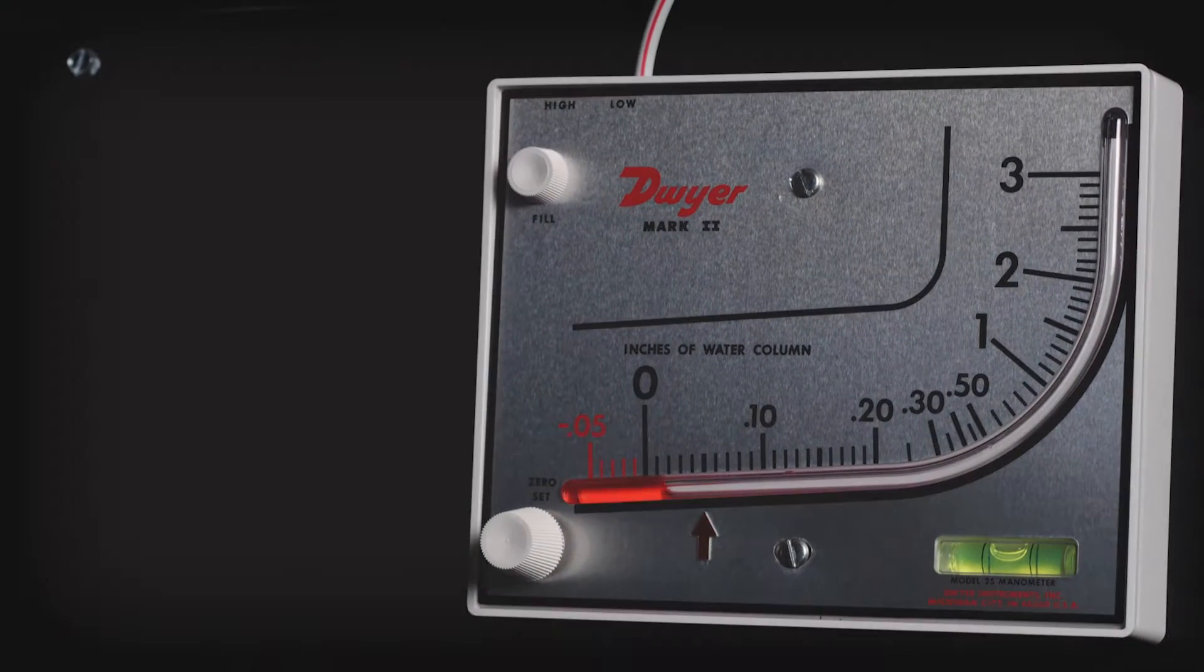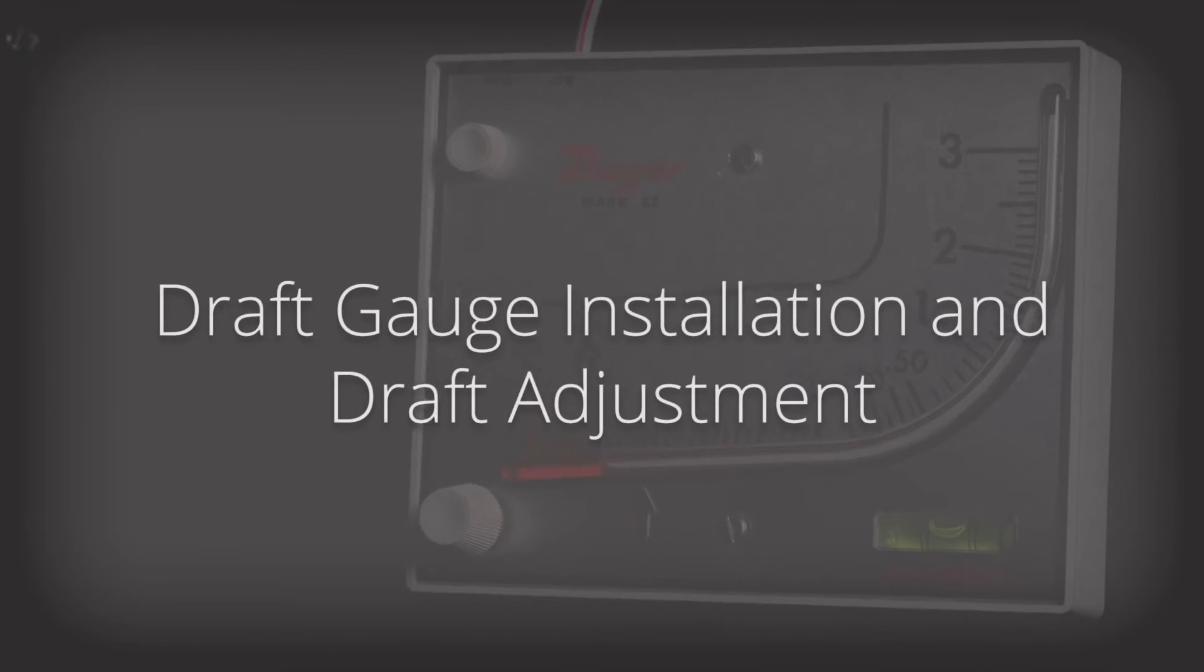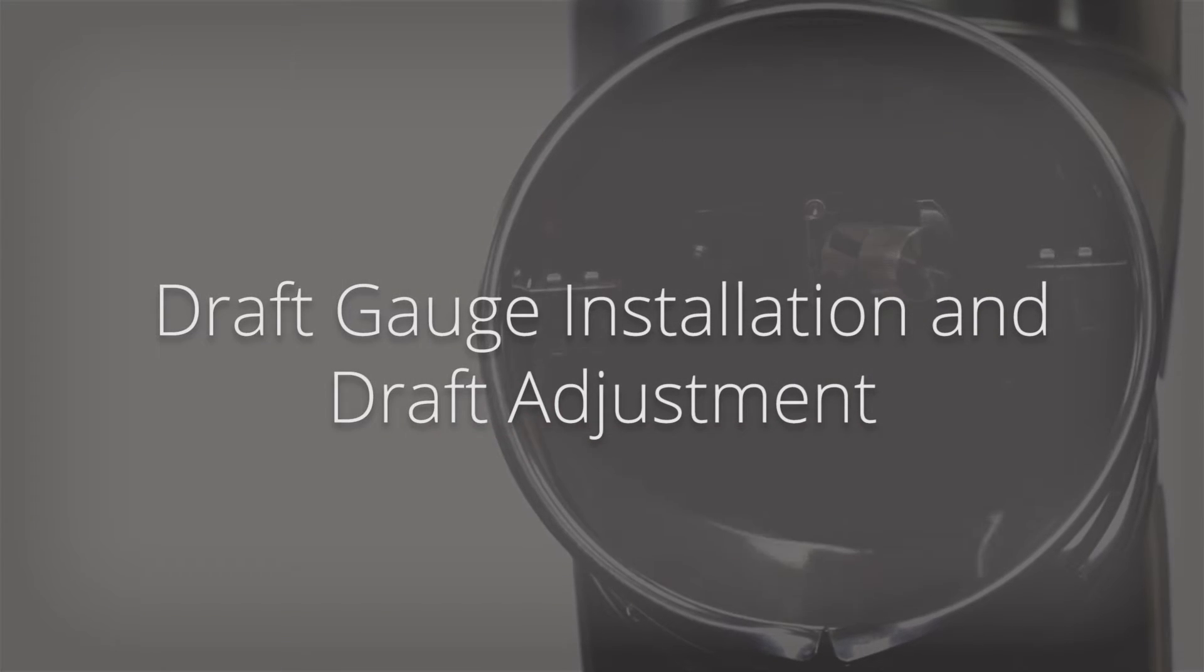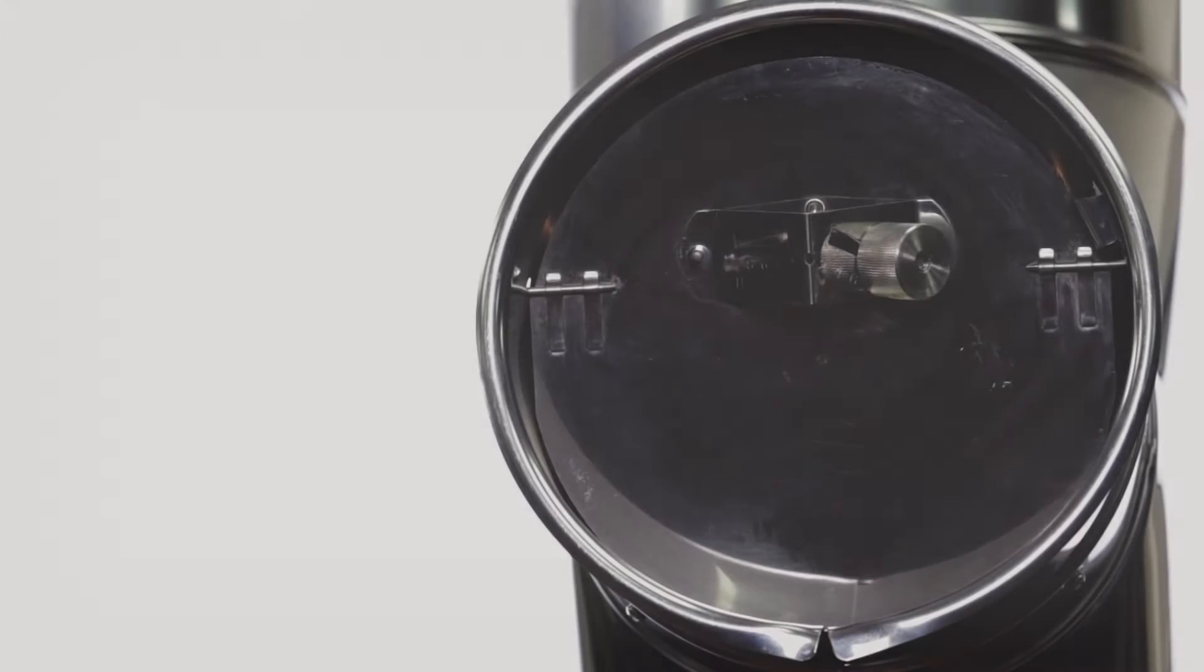In this video, we'll explain proper draft gauge installation and draft adjustment for EnergyLogic waste oil furnaces. Draft is negative pressure in the furnace created by the hot exhaust gases rising up the flue pipe.